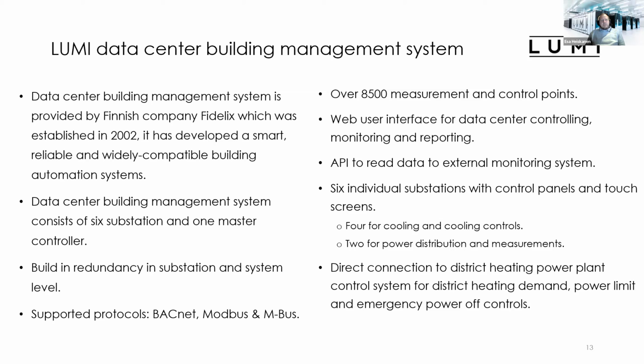The data center building management system consists of 6 substations and 1 master controller, but each of these 6 substations can be operated individually and alone without commands from the master controller in case of failure. There is redundancy at substation and system level, and the supported protocols in this system are BACnet, Modbus, and M-Bus. Most of our devices communicate with Modbus into the building management network. Overall, we have over 8,500 measurement and control points in place.